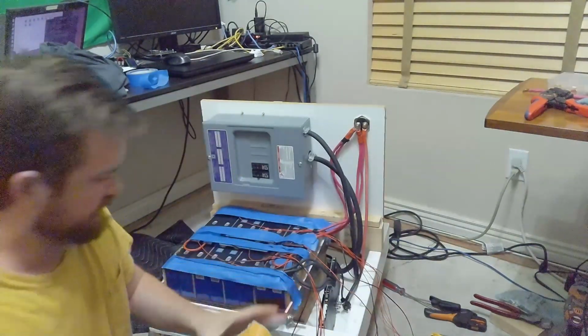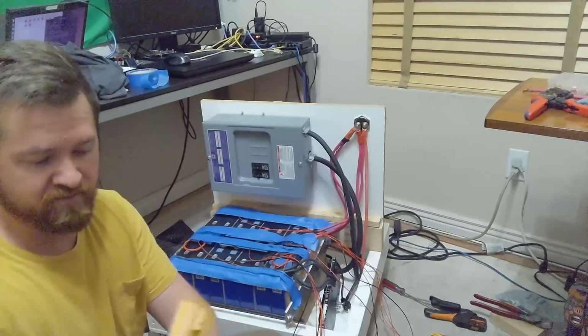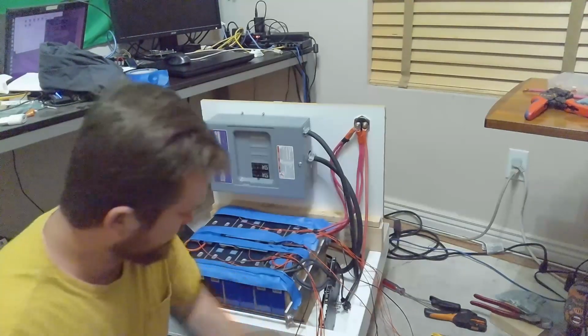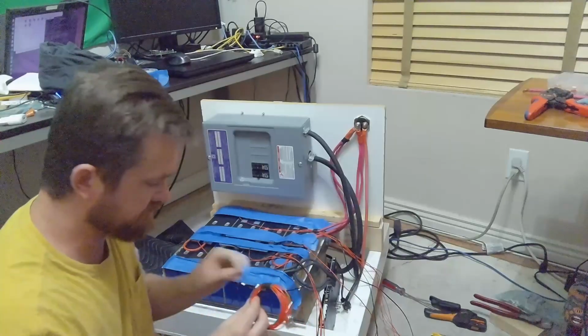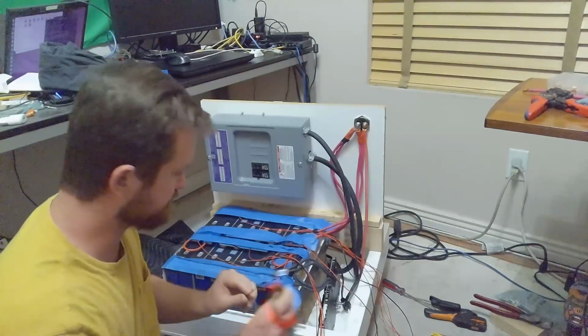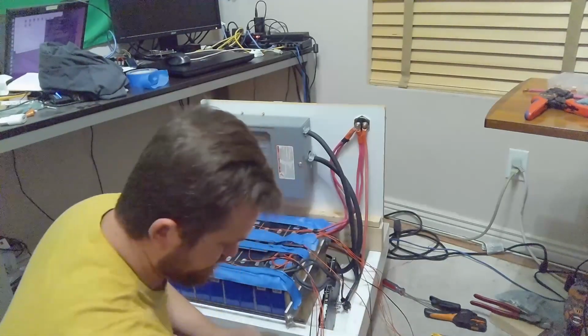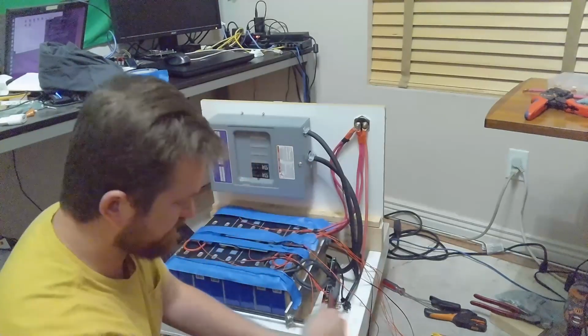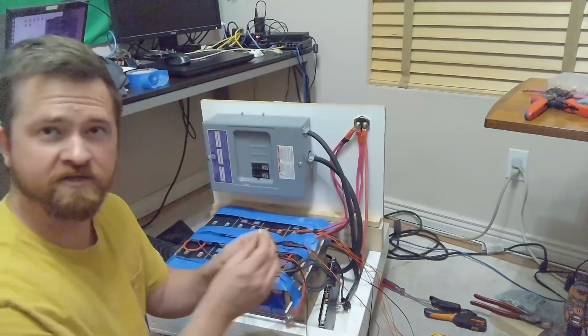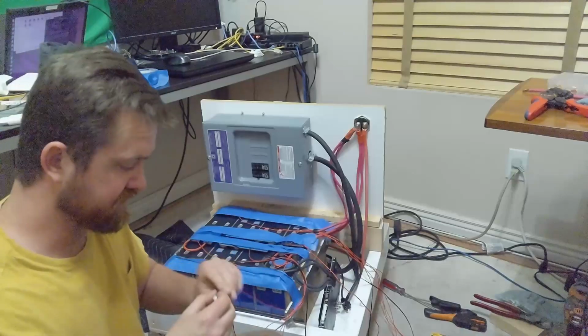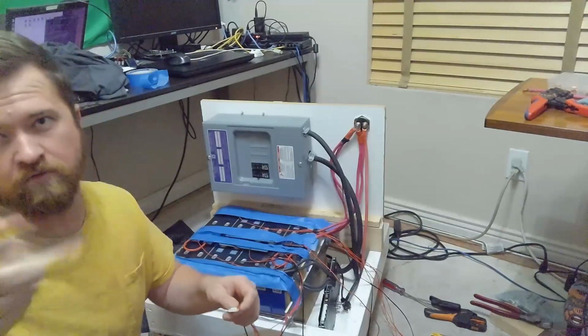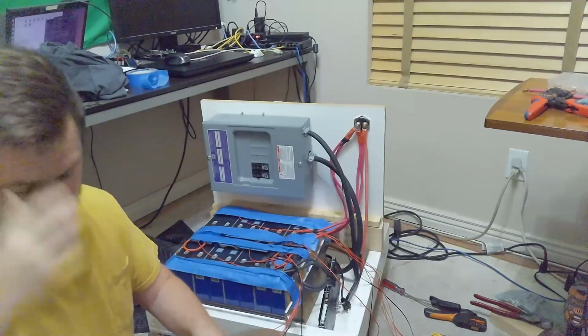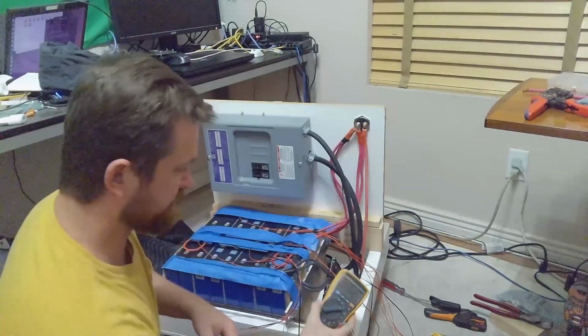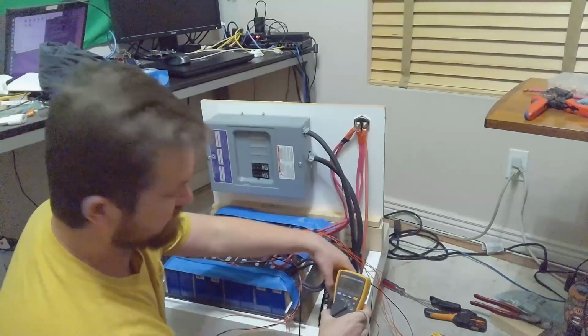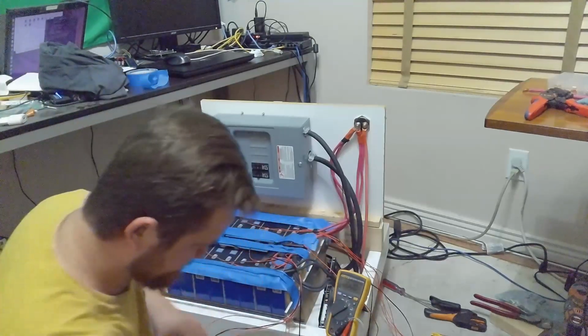Now I want to do a check. I'm going to put this on DC and start at my lowest string, which should be this one with the number—that's number 3, so I need number 1. I should be able to walk up these exposed pins and measure the voltage to make sure I don't have a wrong jump. It should jump by around 3-ish volts every time. I'm not sure how I'll set the meter up so the camera can see it and I can too—I'll try to put it there.